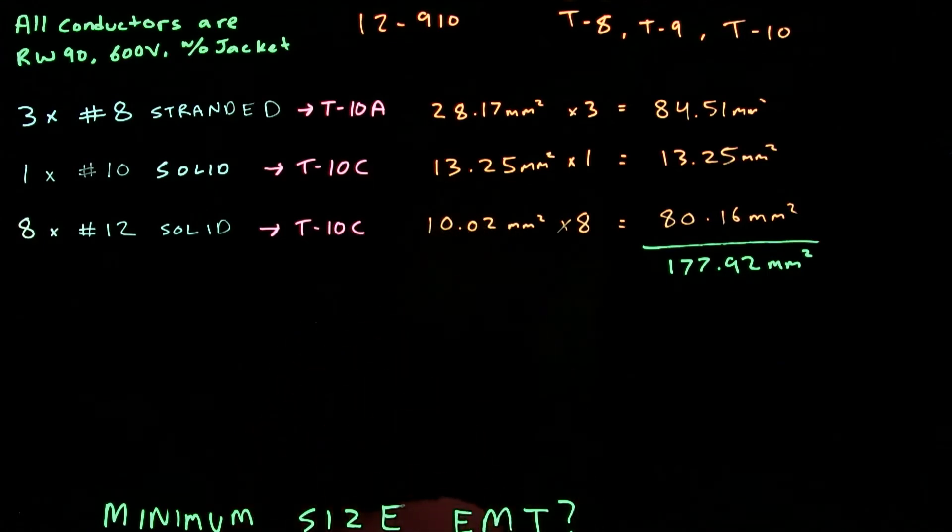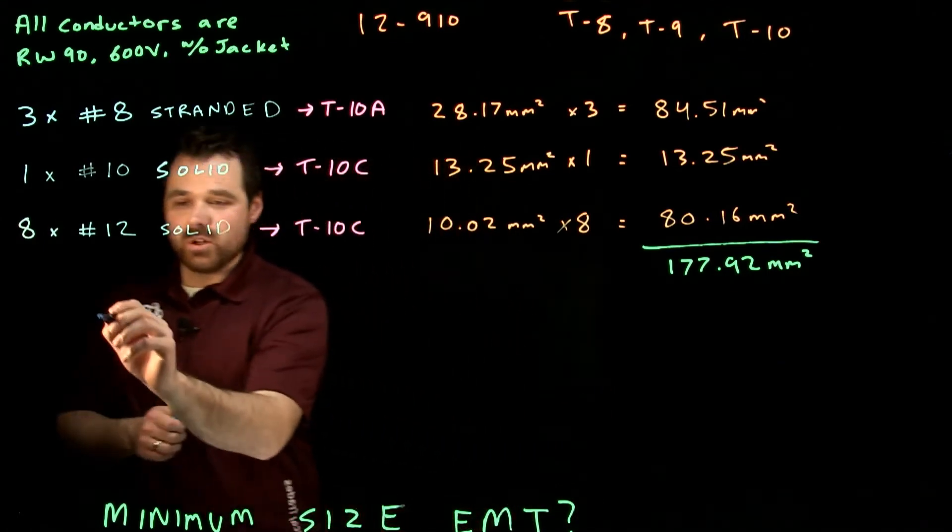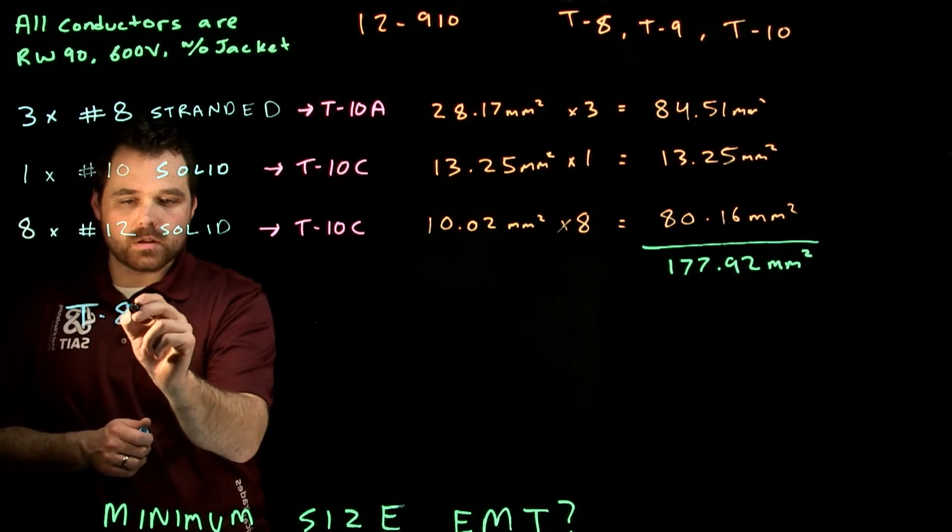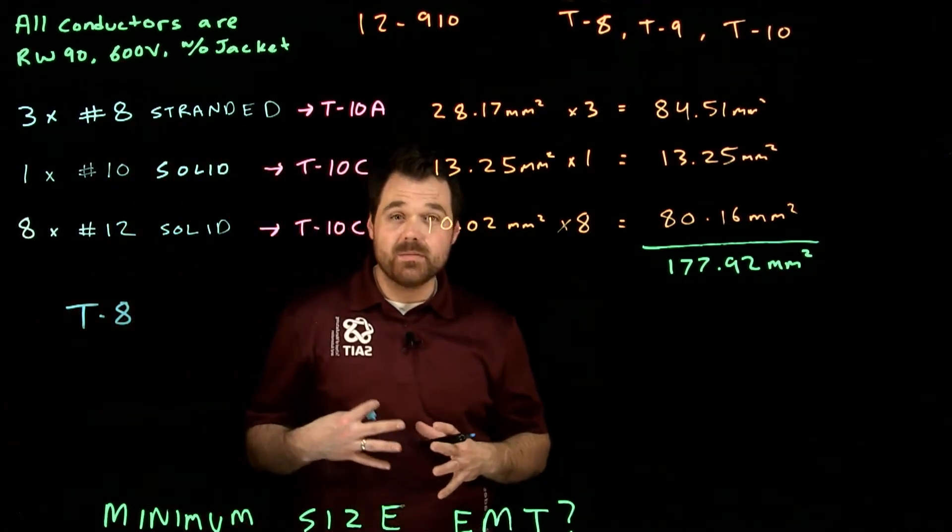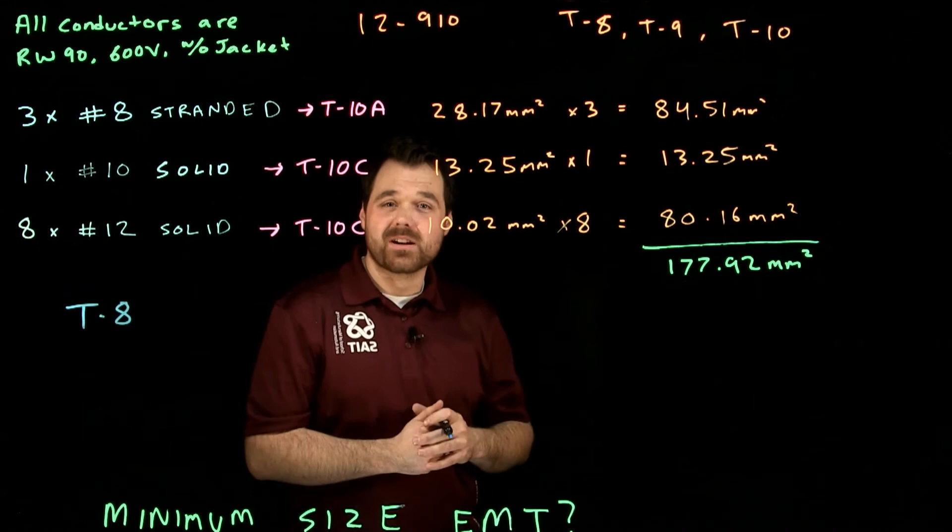Now I have two more steps. First, I need to go to table 8. Now what table 8 is going to tell me is table 8 tells me how much I can fill up that conduit.